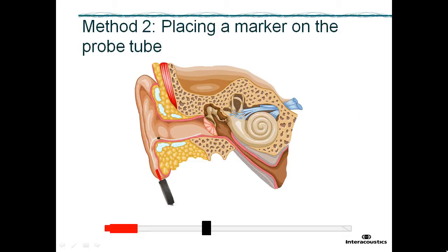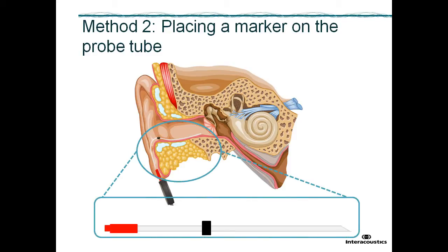Method 2. Placing a marker on the probe tube. The average adult ear canal is approximately 30 to 35 mm long. Therefore, one can estimate ideal probe location by placing a marker on the probe tube. Probe tubes are typically manufactured with a slide marker. The probe tube can then be inserted until the marker reaches the intertragic notch. Some public REM recommendations suggest using a marker of 27 mm from the end of the tube.